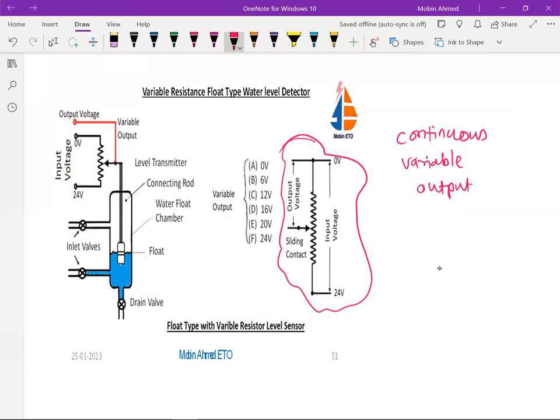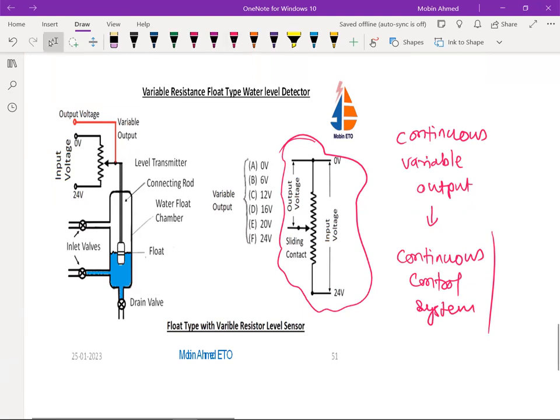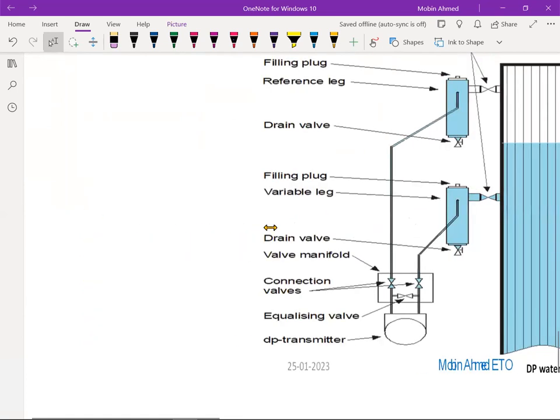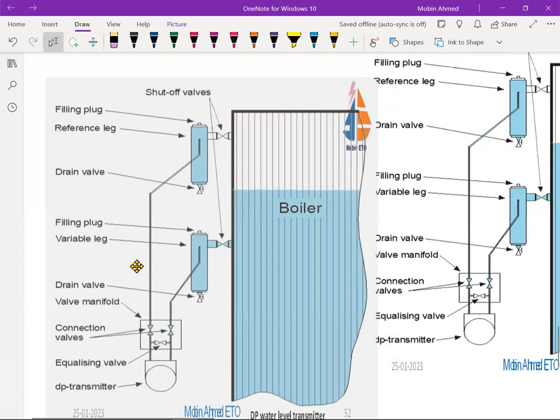And if it is going to give continuous variable output, that means this can be used for a continuous control system, continuous control systems. So with this, we can use for start and stop of the pump. Again, we can use for alarm purposes. So this can also be used. Okay. Working principle is going to be the same. Now there is a last one, that is the DP transmitter. So if you see the DP transmitter here, this is a DP transmitter.